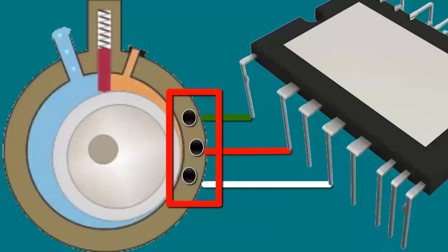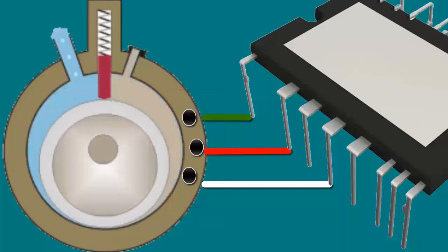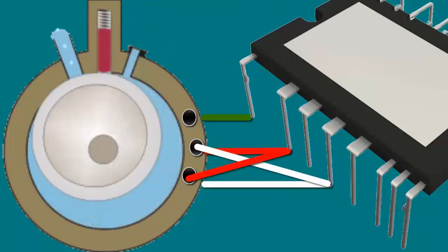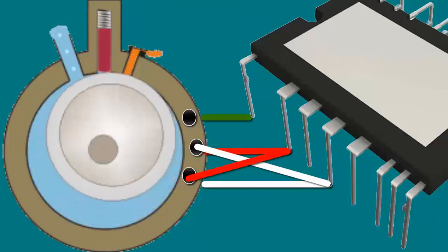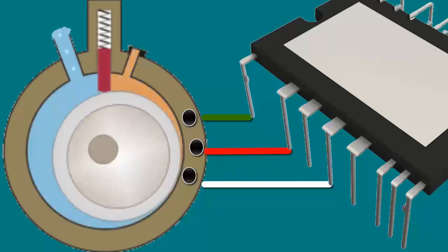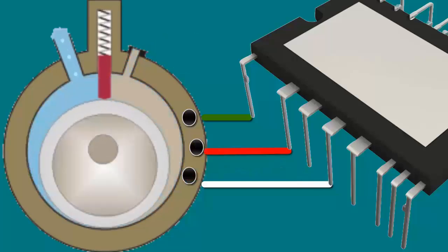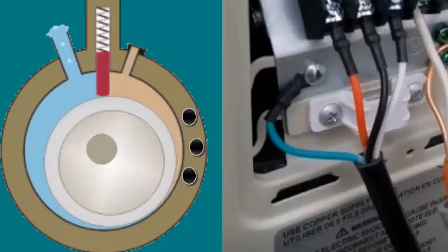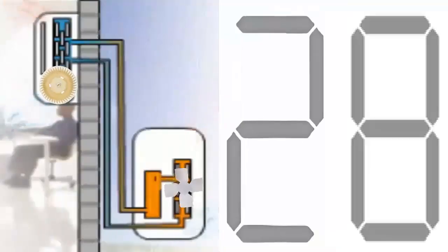Another reason that generates the F28 code is incorrect connections, either in the compressor or on the main board, concerning the UVW order. Another cause of the F28 code is when the connection cables between the board and the compressor are burned or disconnected.